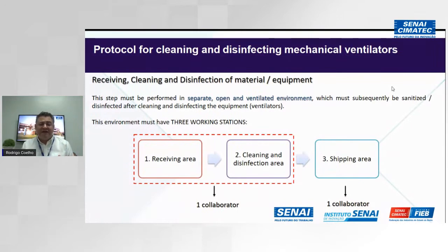So it's very important to have completely different areas: one where we receive the equipment, a second area where we do the cleaning and disinfection of the equipment, and a third area, what we call the shipping area, which follows the whole maintenance steps. These must be completely separated areas, in open and ventilated environments, so that the virus or any kind of bacteria that can be on this equipment will simply spread along the air and not be confined together with our employees. This is very, very important at the stage of receiving and doing the first cleaning of the equipment.